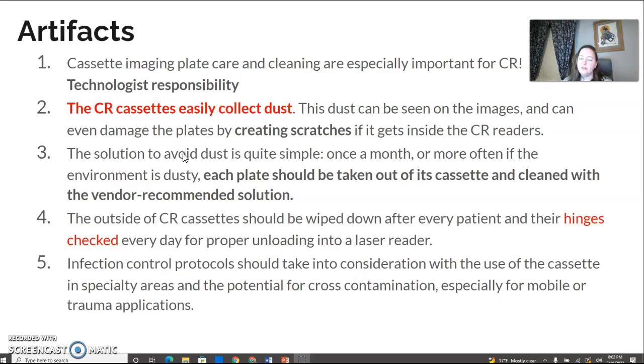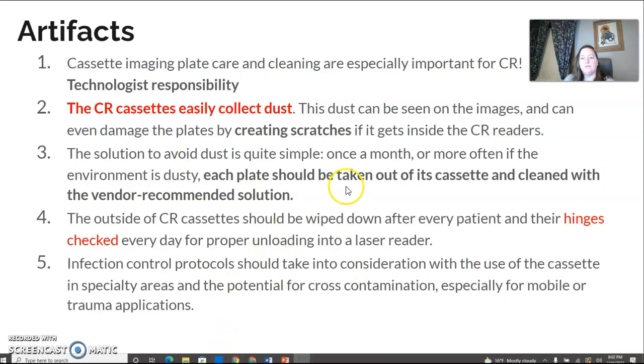Watch for any scratches. If you see something on your image like a bright white line through the anatomy, it's most likely a scratch on the CR imaging plate itself — part of the protective coating might have gotten scratched off. It should be cleaned with a solution assigned by the vendor, whatever they specified. They should be wiped down after every patient for basic infection control.